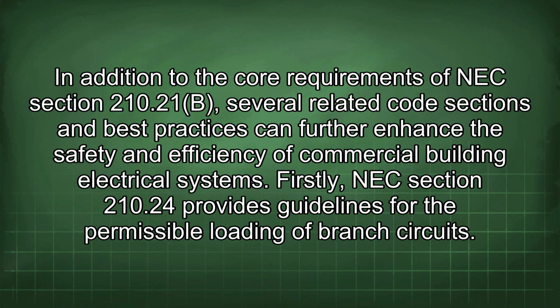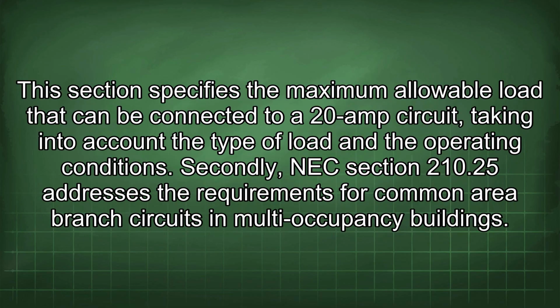In addition to the core requirements of NEC Section 210.21b, several related code sections and best practices can further enhance the safety and efficiency of commercial building electrical systems. Firstly, NEC Section 210.24 provides guidelines for the permissible loading of branch circuits. This section specifies the maximum allowable load that can be connected to a 20-amp circuit, taking into account the type of load and the operating conditions.